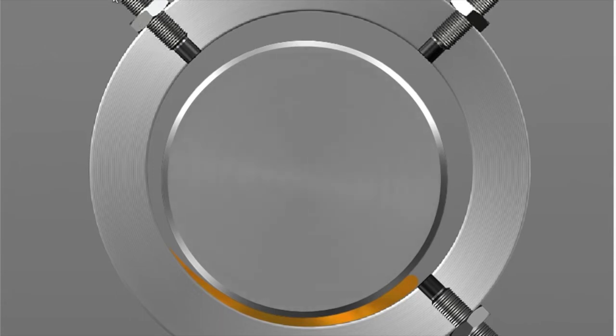These two probes are sensitive to the distance between the tip and the shaft. So as it moves in this direction, this one picks it up, moves in that direction, this one picks it up. We use it to triangulate. These two probes are mounted 90 degrees apart, and we triangulate the motion of the center of the shaft. I'll explain that a bit more in a second.